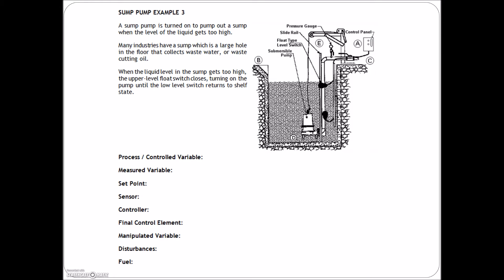Next one is a sump pump. We've got a sump pump with a float switch — when the liquid level in the sump gets too high, the upper level float switch closes, turning on the pump until the lower switch returns it to shelf state. So we have two limit switches, a high and a low limit, controlled by a small control panel. What we're trying to control is level — we're trying to control the level in the sump pit. We've got two float switches directly looking at the level in that tank.